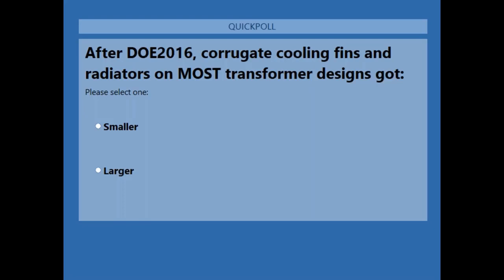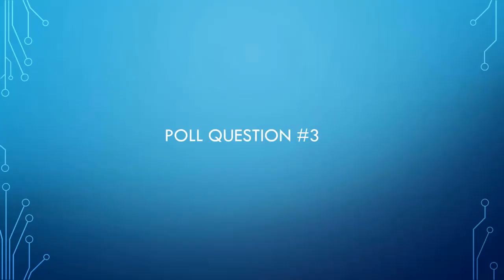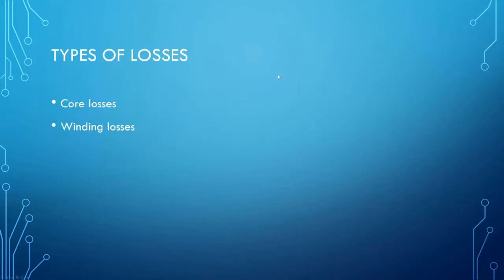DOE 2016 required the efficiencies to go up in transformers. That means the losses had to go down. That means the transformer generates less heat than a transformer manufactured in 2015. Okay, I'm going to close the poll. Thank you so much for answering. If you answered smaller, you would be correct. There's less heat to remove with a 2016 DOE transformer. Therefore, the corrugation and the radiators can be smaller. The expense goes into the core and coils to make them larger, heavier, and more efficient.